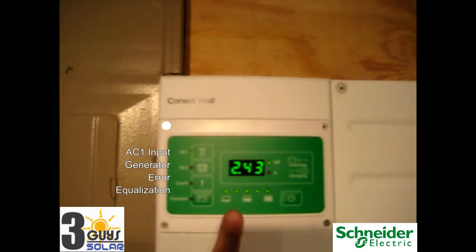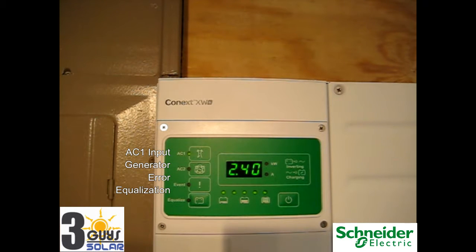to protect itself and to protect the loads. In grid-tied selling during the day while you have excess energy, this will display the amount of kilowatts, that is, the amount of watts divided by 1,000, of energy that is being converted excess off of the batteries and sold into our existing load panel. When it is selling, the kW light will be flashing, and the numbers you're seeing are the actual amount of kilowatts. So currently we're running about 2,000 watts of exported energy.